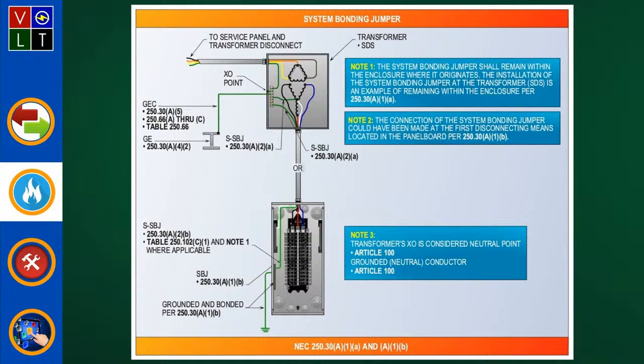Once you get above that size, the system bonding jumper shall be sized at least 12.5%, or 0.125, of the circular mil area of the largest ungrounded phase conductor, where these service conductors are larger than the 1100 kcmil copper or 1750 kcmil aluminum.